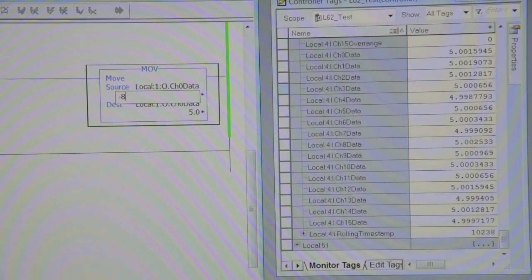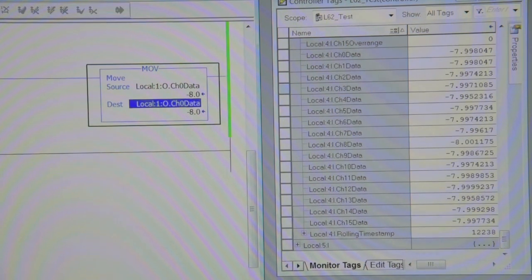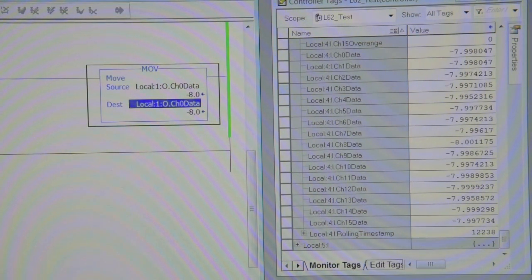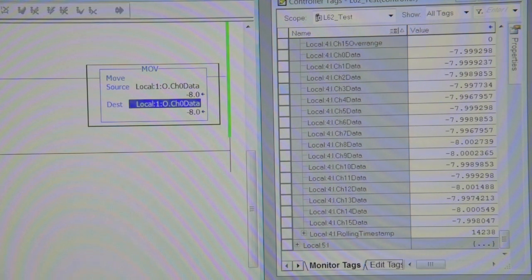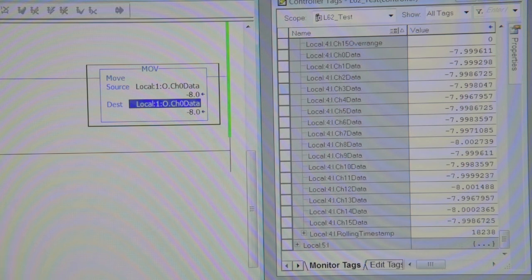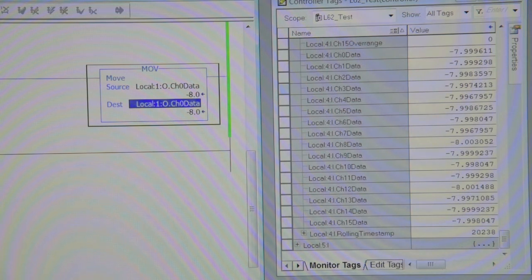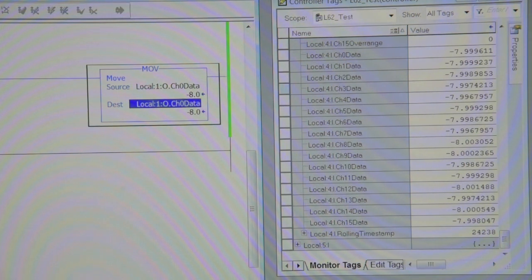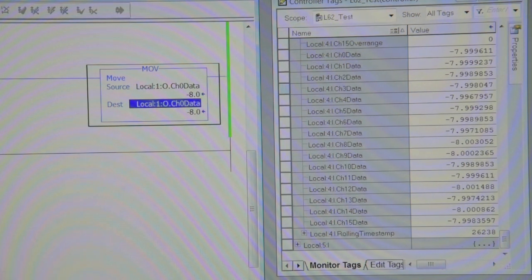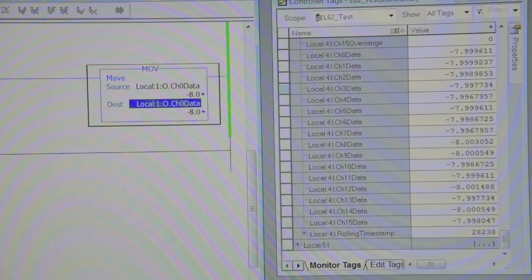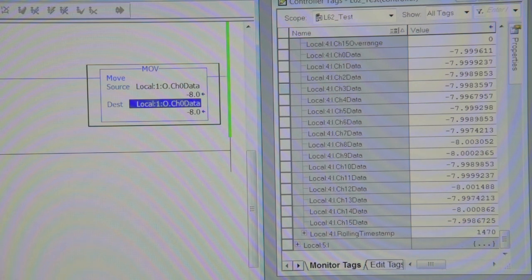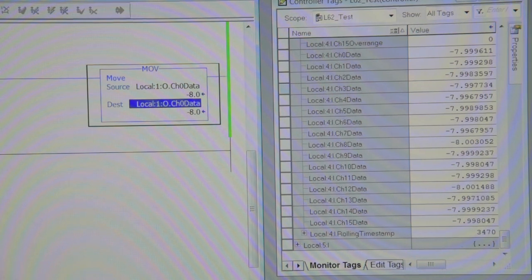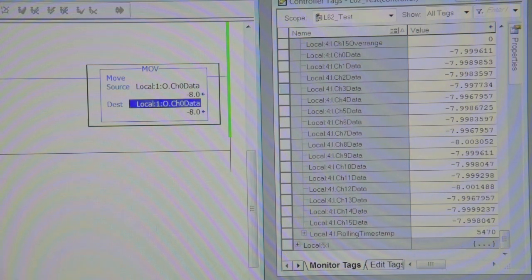Again, if we go minus 8, just is a pretty decent number to work with. We're putting minus 8.01 volts on our Fluke 123. We're reading between minus 7.999, 997 and 8.001. Again, that's acceptable for this sort of module.